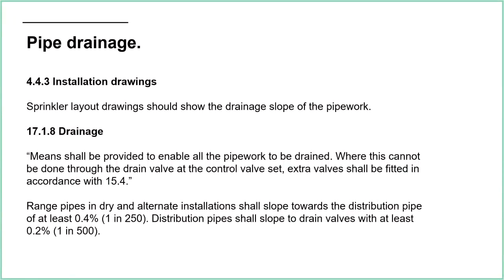For dry and alternate installations, there actually is some information in terms of what slope we need to allow for. So range pipes of 0.4%. I converted that into 1 in 250, which makes more sense to me than a percentage. Distribution pipes will slope to the drain valves with at least 0.2%, which is 1 in 500. So for dry and alternate installations, there are specific slope requirements that need to be met. For wet pipework, it's basically down to the designer to make sure that all the pipework is able to be drained.